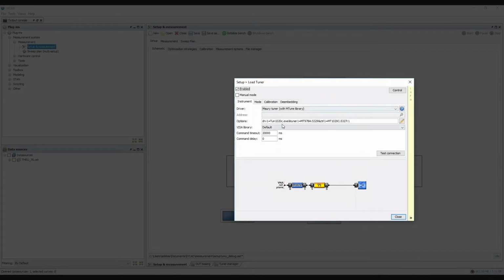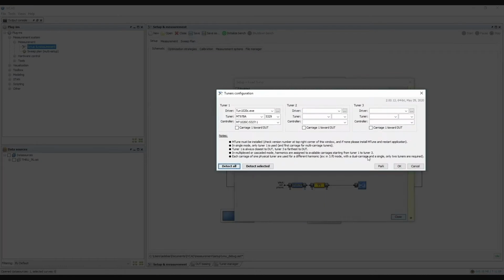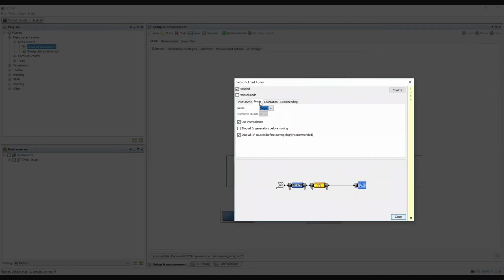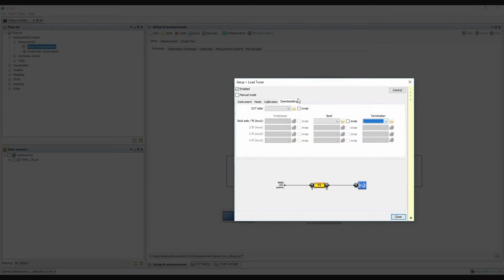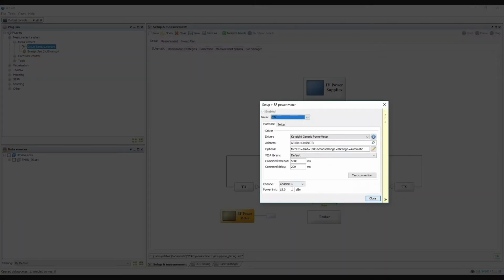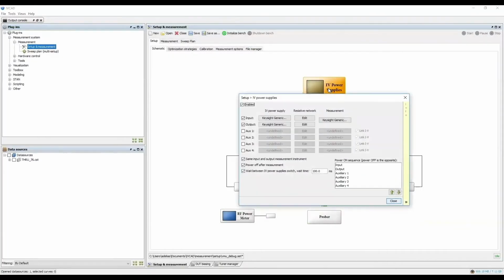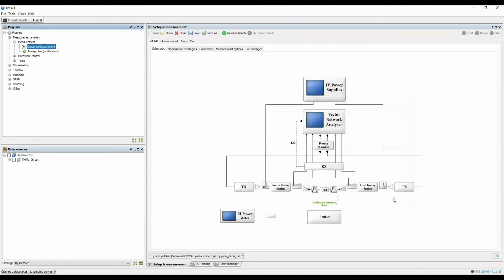Then, the load tuner is configured in exactly the same way as for any other load-pull measurement in IVCAD. After that, we configure the power meter, which will be used during the system calibration, and the IV power supplies that will be used to bias our device under test. When each individual instrument is configured as desired, we can start the system calibration.